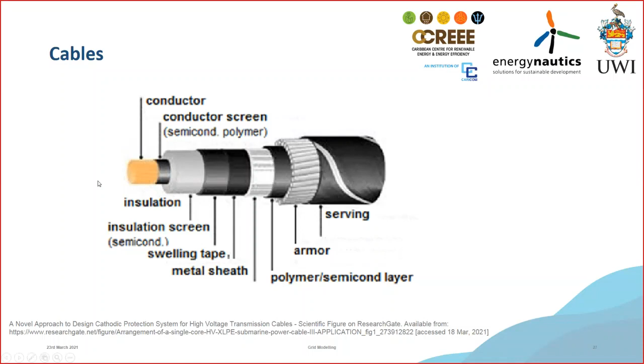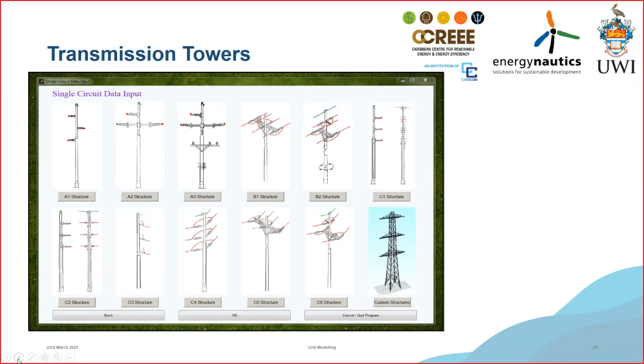The other model that we have to look at is our transmission tower design. If you notice, we have shown on this structure here, we have 12 different designs. And each design, let's look at this B1 structure, the coupling between each phase is completely different to the coupling between each phase here. And therefore, by extension, although I may use the same conductors on both structures, let's say the B1 and the B2 structure, the actual impedance as seen by the network by these two different structures is going to be different because the magnetic coupling between the phases is going to be different. So in getting the cable's impedance for doing your analysis, I must also know what the tower structure is, because that's how the conductors are stranded across your system. So that's where my impedances are going to change for the same type of conductor.